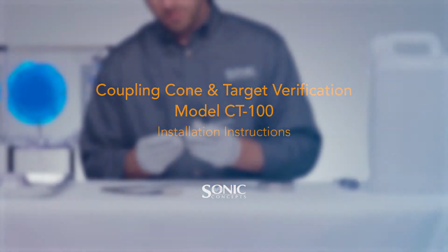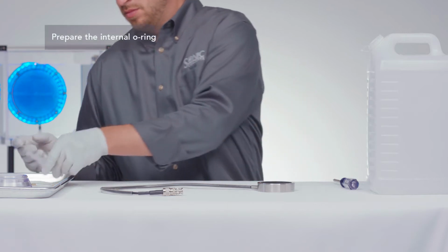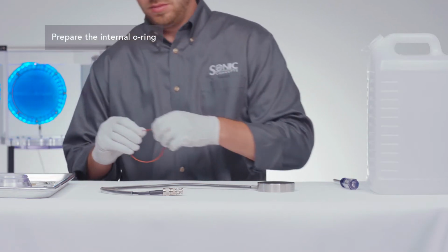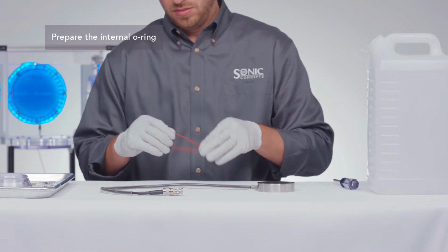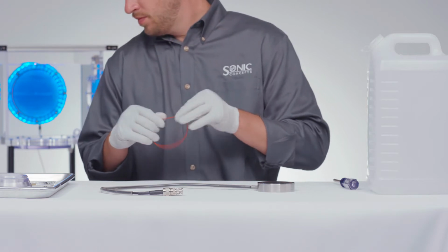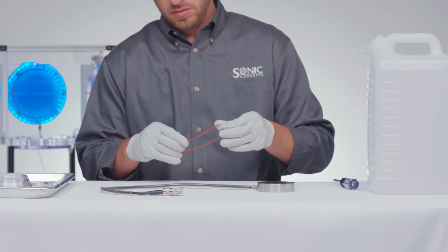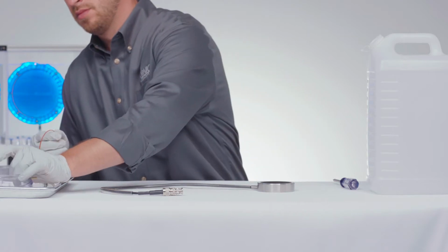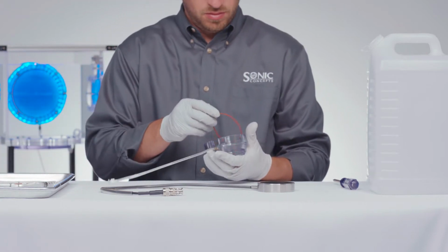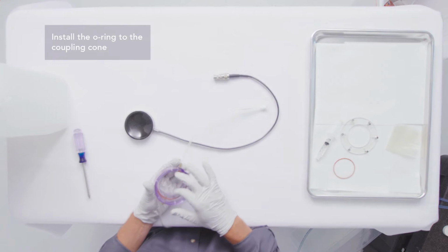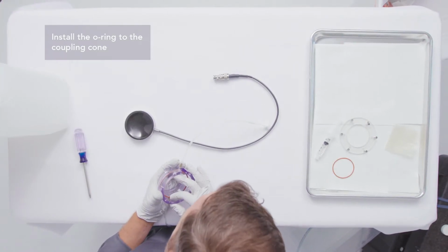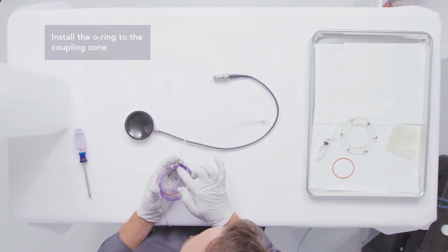CT-100. To ensure a watertight seal between the transducer's housing and the CT-100 coupling cone, dispense a small amount of O-ring lubricant to your fingertips and thoroughly coat the internal O-ring. Once fully lubricated, install the internal O-ring until it's properly seated within the coupling cone's inner groove.